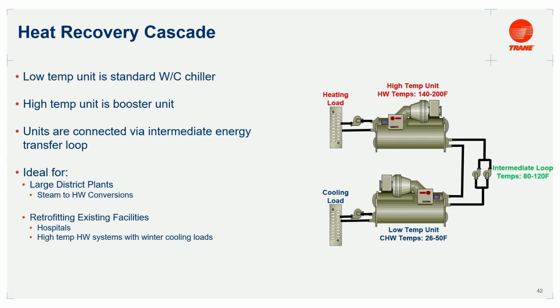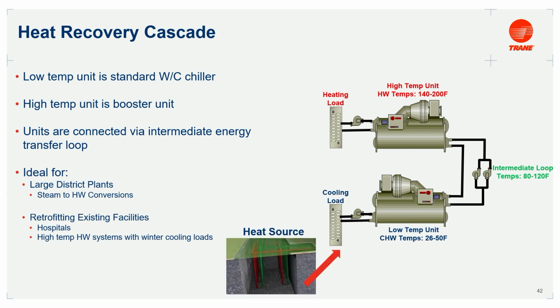We're going to talk about heat recovery cascades. This is not for every job. It's not meant to be for every job. A great example might be large district plant steam to hot water conversions, campus level conversions. You've got 20 buildings that need 180-degree water. We can do that with a single compressor, but is that really the right way to go? If we hook up to a geothermal loop as our heat source, do a standard set of lift, maybe 45 in, 35 out, back to the well field, get about 110, and put that into the evaporator of another chiller heater, which is the same Trane centrifugal we've been making for years. It's not new technology for our techs.